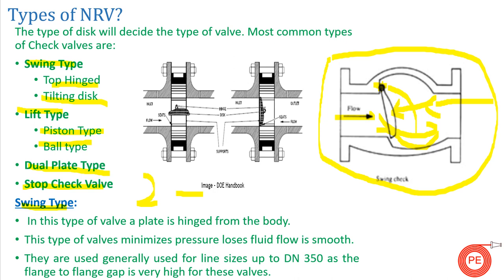Swing type valves are used in pump discharges or compressor discharges. However, the limitation of a swing check valve is the flange-to-flange gap — as the pipe size increases, this gap becomes very large. For sizes greater than 350mm with space constraints, we generally go for a counterweight dashpot type valve instead. The key benefit of the swing check valve is that it minimizes pressure losses and fluid flow is smooth.